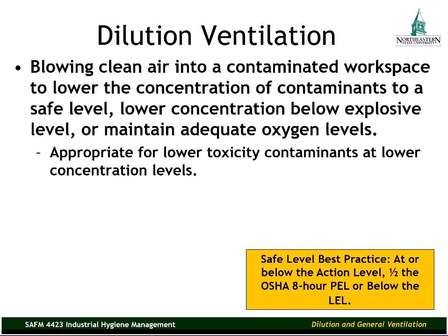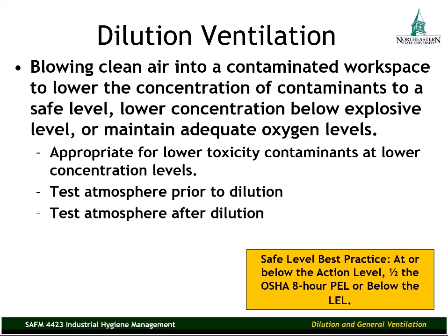When we're using dilution ventilation, one of our first steps is to test the atmosphere to see what our level of contamination is. Then once we get the ventilation system running, we want to test the atmosphere after it's been diluted.